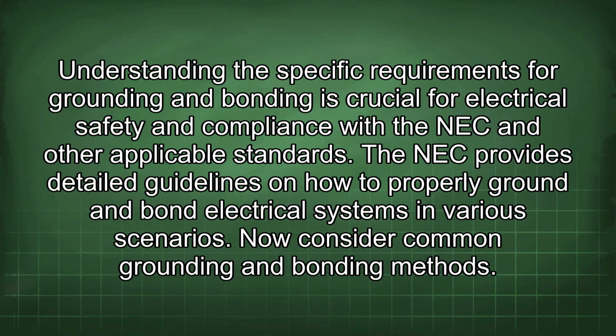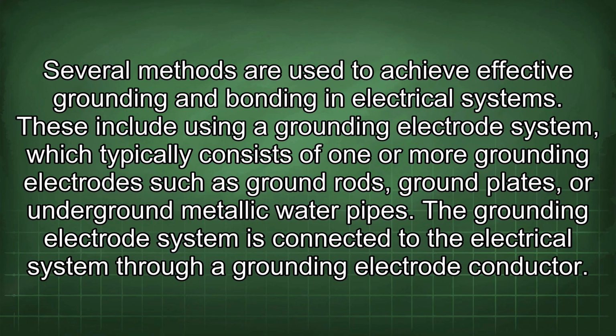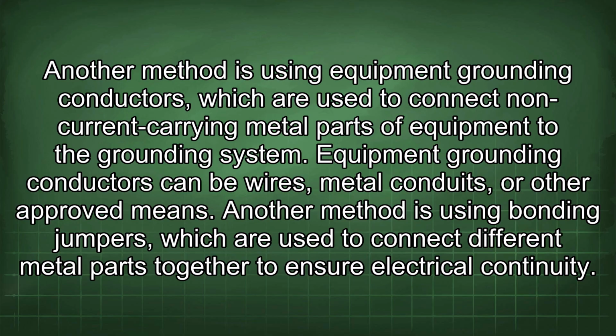Now consider common grounding and bonding methods. Several methods are used to achieve effective grounding and bonding in electrical systems. These include using a grounding electrode system, which typically consists of one or more grounding electrodes such as ground rods, ground plates, or underground metallic water pipes. The grounding electrode system is connected to the electrical system through a grounding electrode conductor. Another method is using equipment grounding conductors, which are used to connect non-current carrying metal parts of equipment to the grounding system. Equipment grounding conductors can be wires, metal conduits, or other approved means.